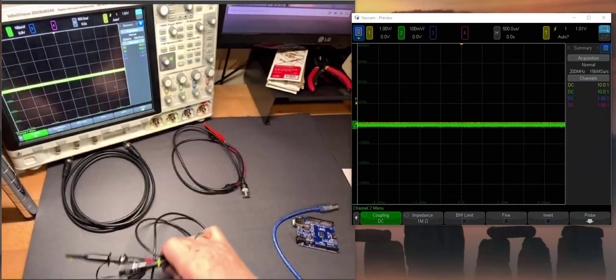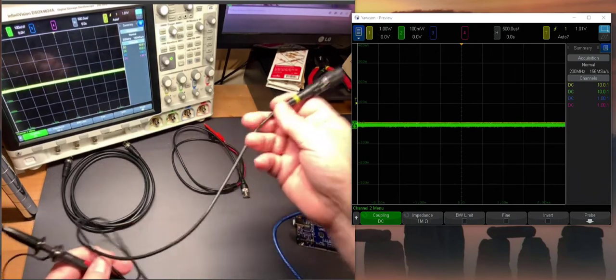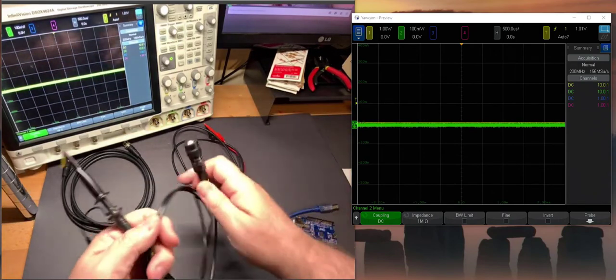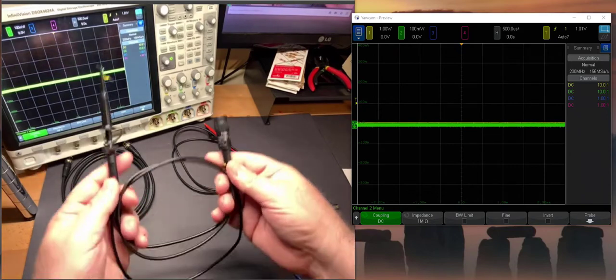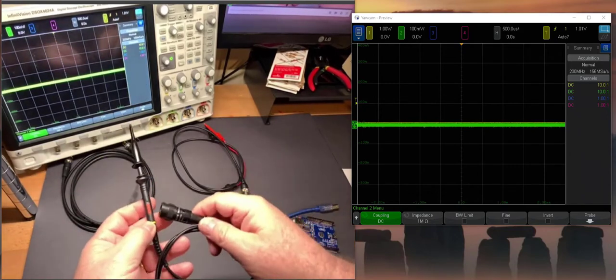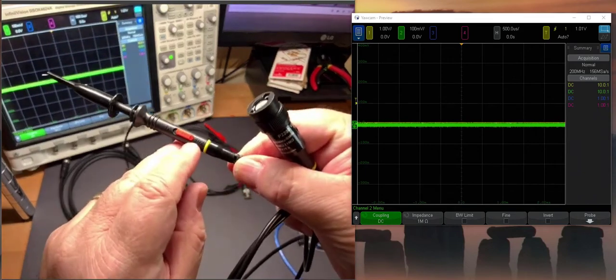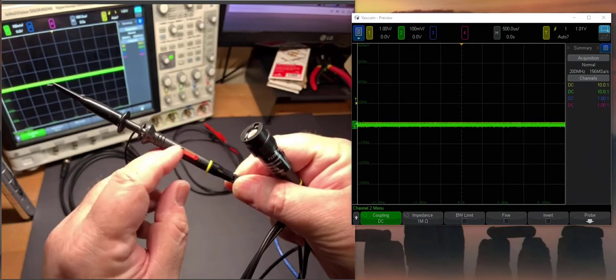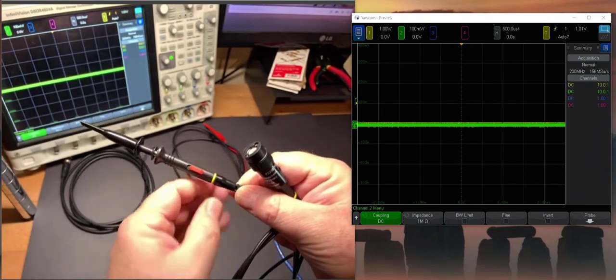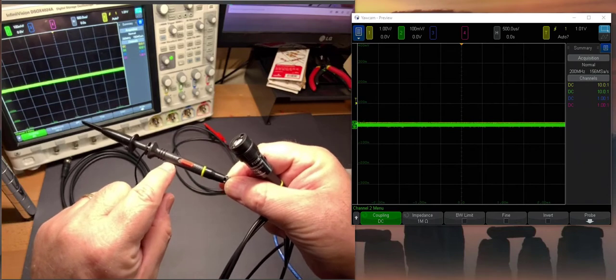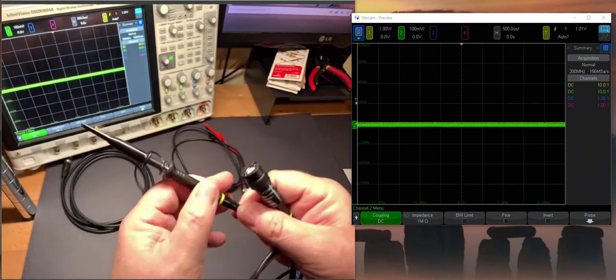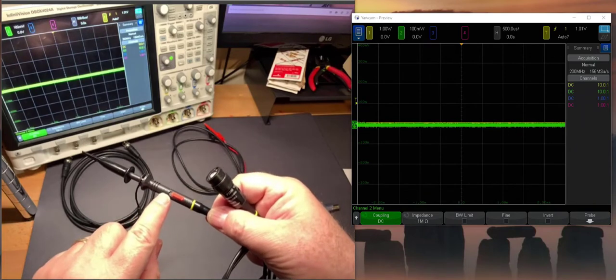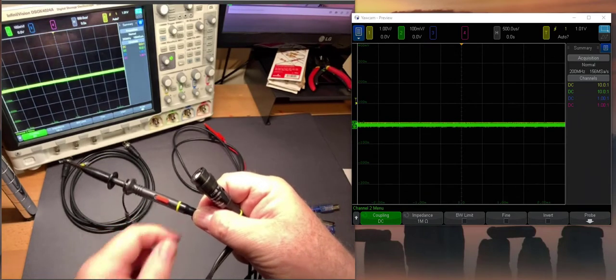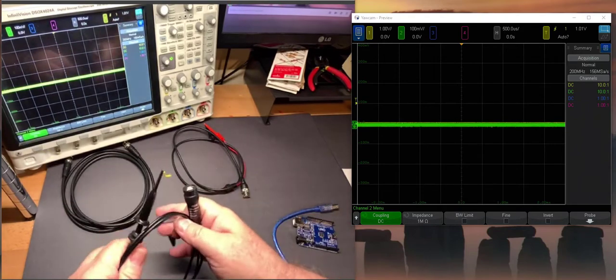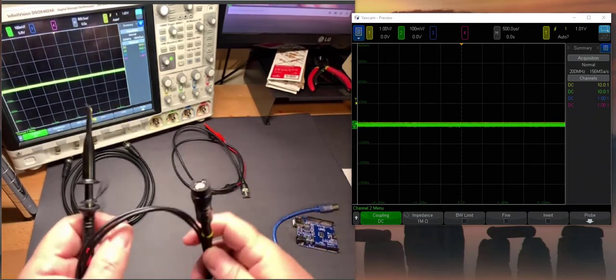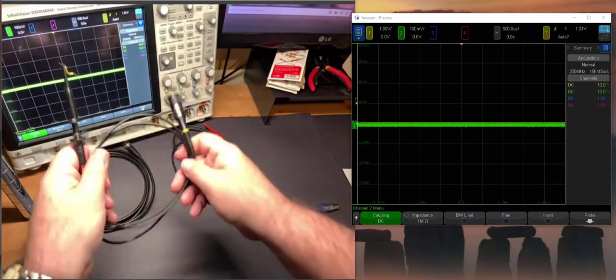And then the third kind of cable we're going to use is also coaxial, but it's a very, very special type of cable. We sometimes refer to this as a 10x probe. You'll notice there's a 10x marking over here. We can slide the end from 10x to 1x. As we will see when we talk about the details of the 10x probe, never ever use the 1x. There is zero reason for it, and we'll see that it distorts the signal quite a bit. So we want to be careful if we ever use that 1x setting. We always want to use the 10x setting. And we'll spend quite a bit of time talking about the 10x probe because it is really the workhorse probe that we're going to use over and over again with the scope.